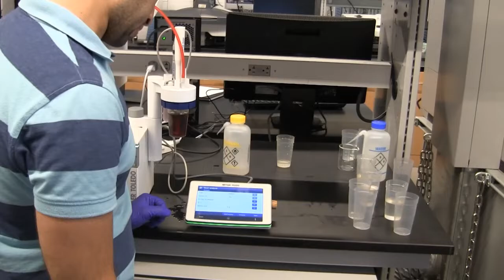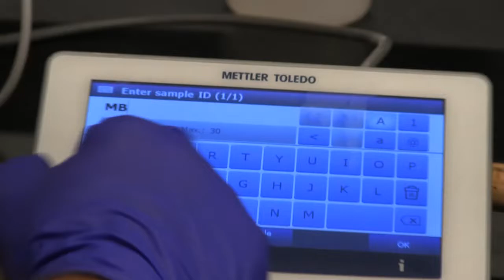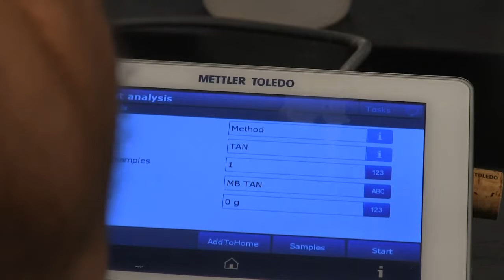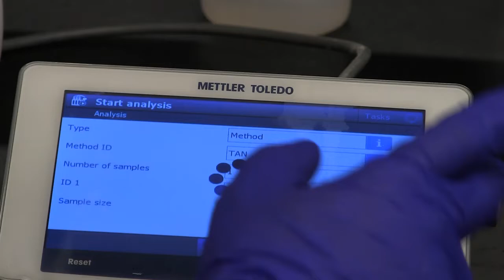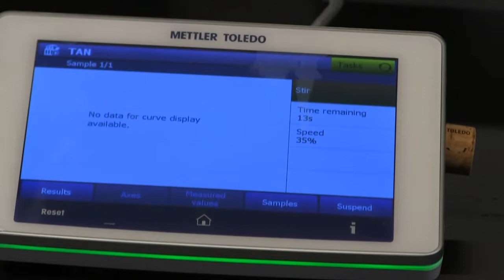So you attach the cup, you choose total acid number or TAN. It will ask you for the sample ID, so you can call it whatever ID you want. Click OK. And the sample size was 10 grams. And try to be precise in here. If there is any fraction, just add it. In our case, it was precise, so we just use 10. And you click start. It says add the sample, so we added the sample.